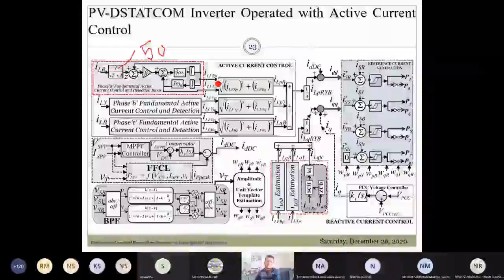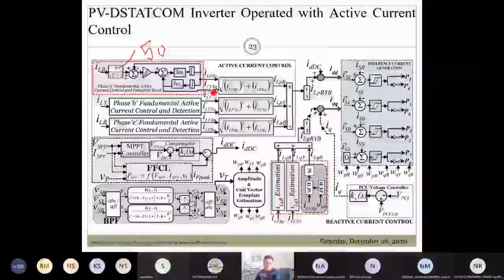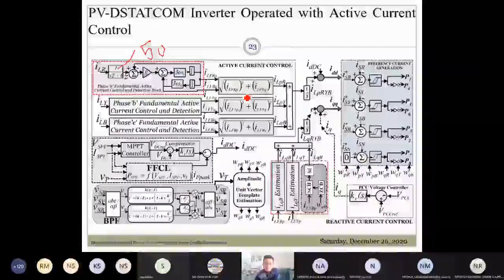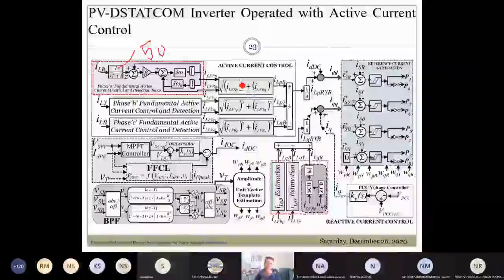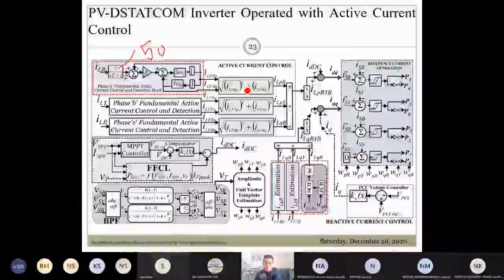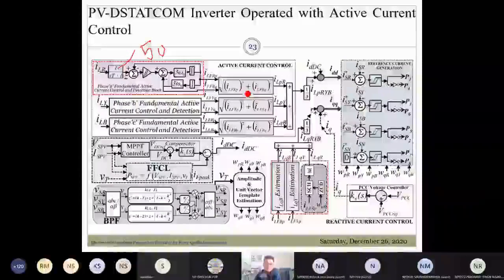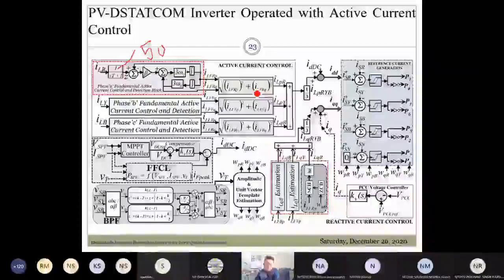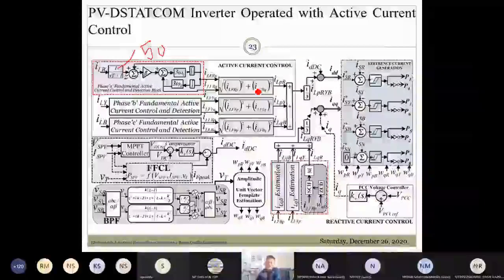Here you have the fundamental signal. This is your fundamental in-phase signal, and this is your fundamental quadrature signal. You might have come across certain research publications where researchers have used a zero crossing detector to detect the phase angle of the input voltage signals. But I have discarded this zero crossing detector, because it is prone to signal jitters, especially when the voltages are contaminated with harmonics, and its response is observed to be sluggish.